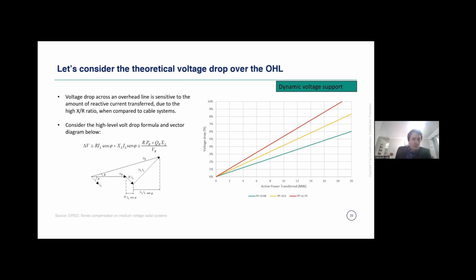So in order to ensure that we didn't need to upgrade this entire line, what we needed to manage was the amount of reactive power that's actually flowing over the line. And considering that it is only the solar PV plant that's injecting across this line, what we ended up doing is ensuring that we set a fixed power factor control mode on the solar PV plant and limit the power factor to 0.98 at all times.